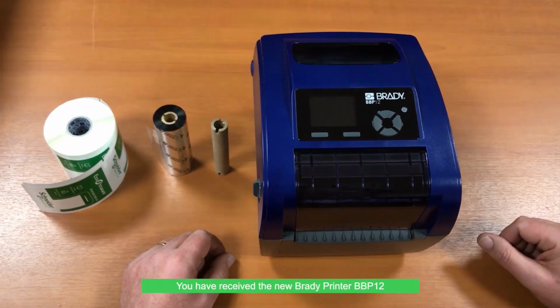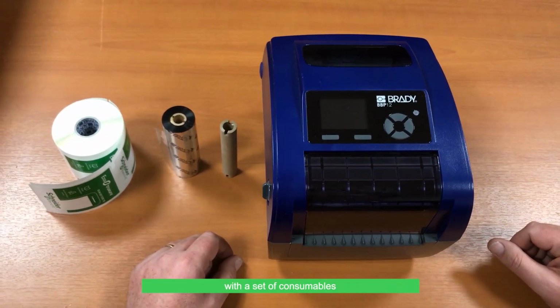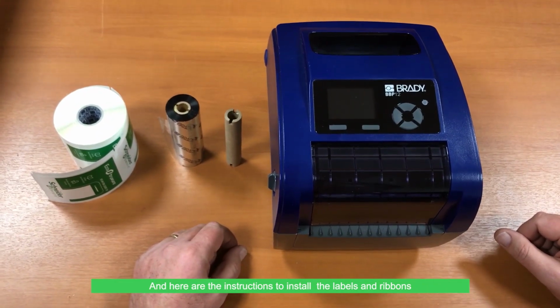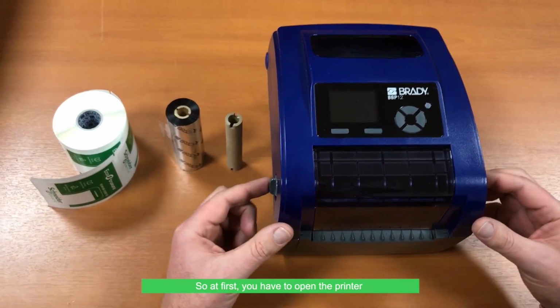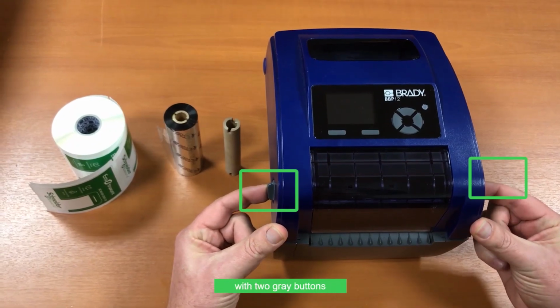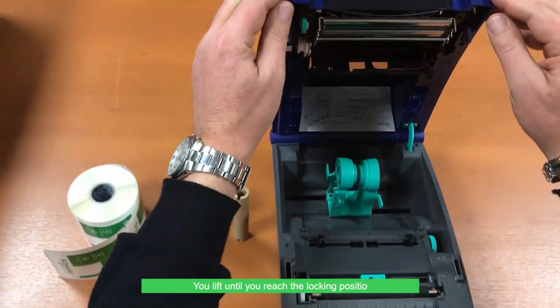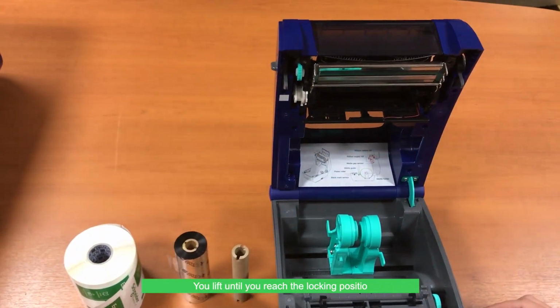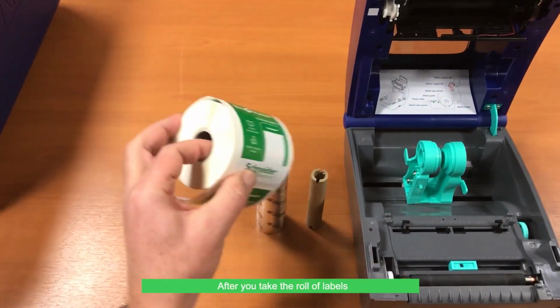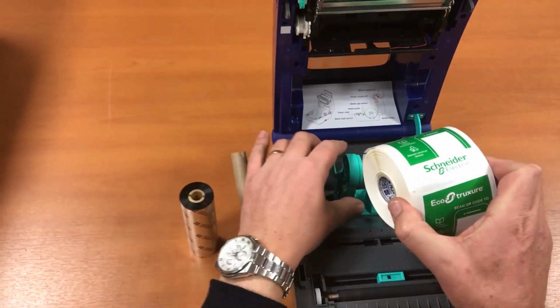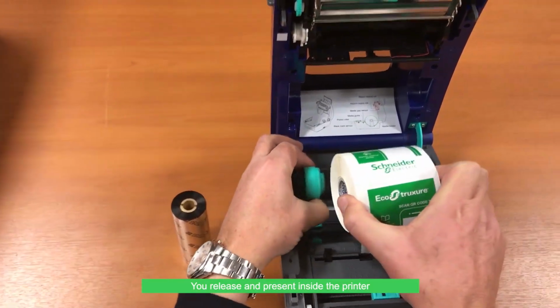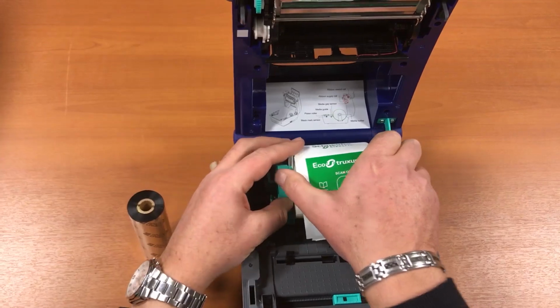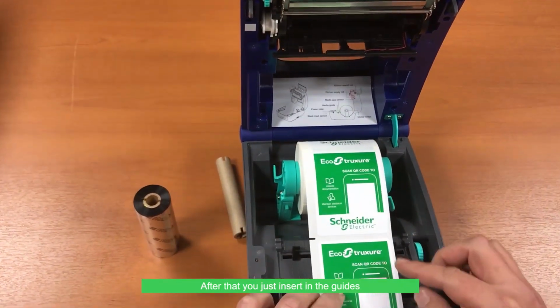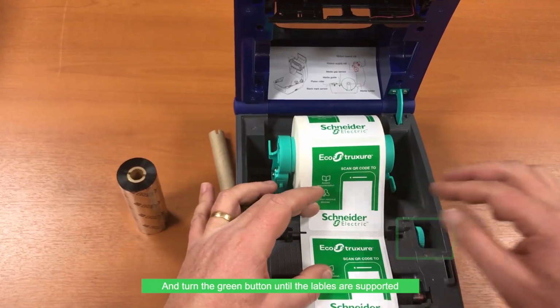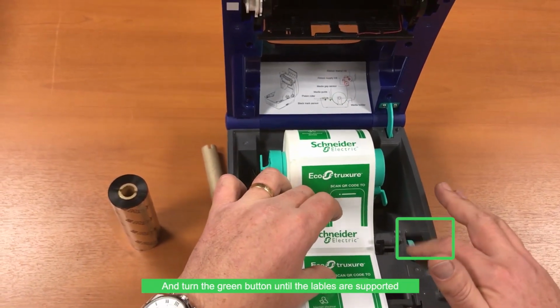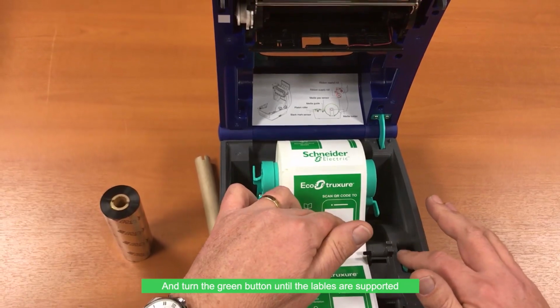You have received the new Brady printer BBP12 with a set of consumables, and here are the instructions to install the labels and ribbons. So, at first you have to open the printer with the two gray buttons. You lift until you reach the locking position. After you take the roll of labels, you release and present inside the printer. After that, you just insert in the guides and turn the green button until the labels are supported.